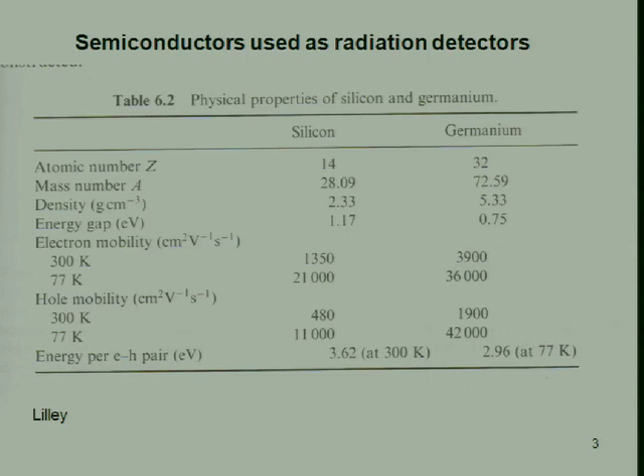The silicon detectors have some advantage over germanium if it's charged particles you're looking for. If you're going to look for electrons or protons or alpha particles, silicon is the preferred way to do it. The reason is that it takes so little energy to make an electron hole pair in germanium. In order to get the best energy resolution you can, you have to cool them to something like liquid nitrogen temperatures. And so this enormous thermos bottle over here is full of liquid nitrogen meant to cool a little crystal of germanium, which is up in here.